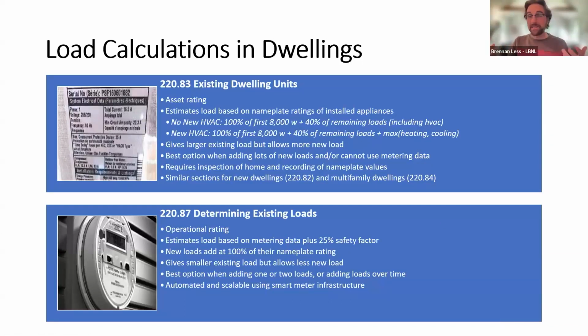See this as kind of an asset rating, right? It wouldn't depend on who's living in the home or anything, and it's not going to change from year to year. It usually gives a larger load, but it has a little more flexibility in how we add new loads. When using this code path, a lot of new loads get treated at 40% of their rated power, so you could potentially add more than double the load because of that 40% allowance. For that reason, it might be a better option when you're trying to add lots of new loads to an existing home instead of just one.